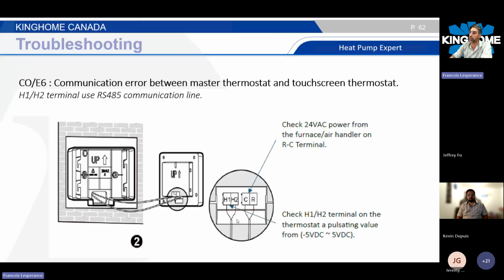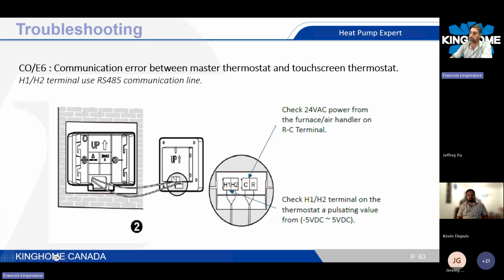So for example, if you don't read it from here, that's maybe because the other thermostat is not properly connected, or there's a break in the wire, there's something wrong with that. If you do have, for example, the pulsating value and the thermostat is still not communicating, then maybe the thermostat can be defective at that point.